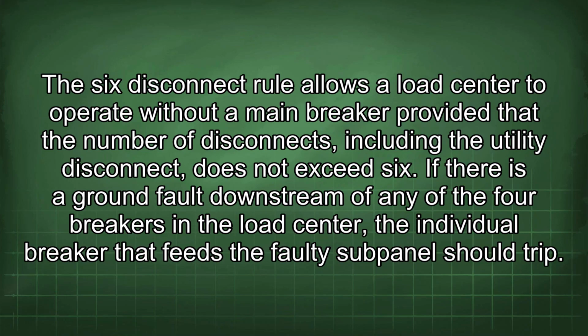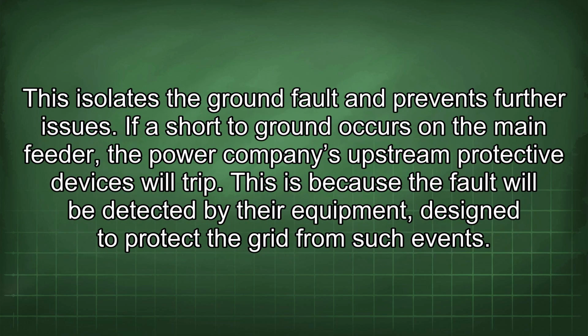The 6 disconnect rule allows a load center to operate without a main breaker provided that the number of disconnects, including the utility disconnect, does not exceed 6. If there is a ground fault downstream of any of the 4 breakers in the load center, the individual breaker that feeds the faulty subpanel should trip. This isolates the ground fault and prevents further issues.